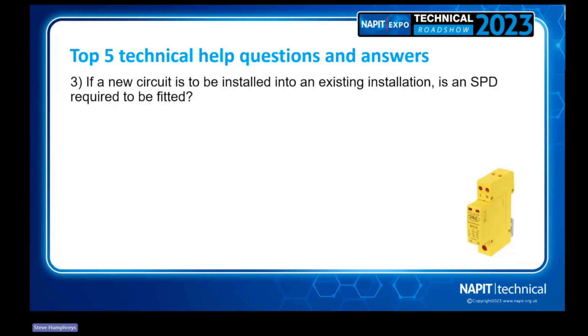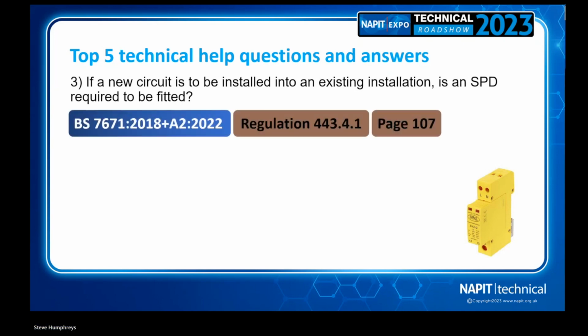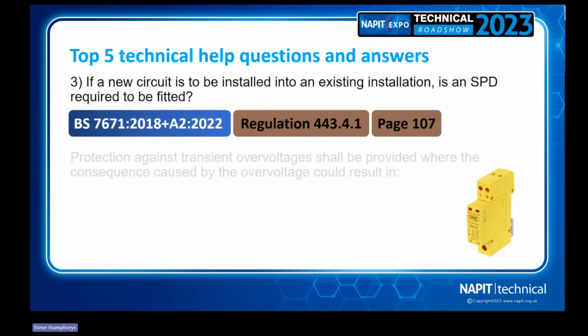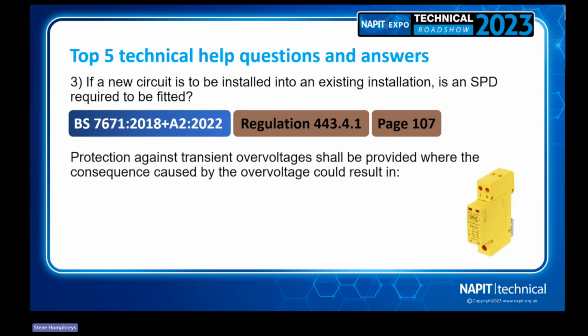Question 3. Again, we've got another device. So far we've looked at them, they've all been ones in consumer units. So if a new circuit is to be installed into an existing installation, is an SPD required to be fitted? Again, we point to the regulation. In regulation 443.4.1 on page 107 of the wiring regs, it says this: protection against transient overvoltages shall be provided where the consequence caused by overvoltage could result in the following. That's worth noticing in that particular sentence. Again, it's not talking about equipment particularly or the circuit itself.